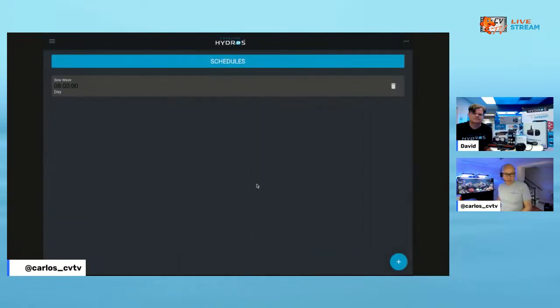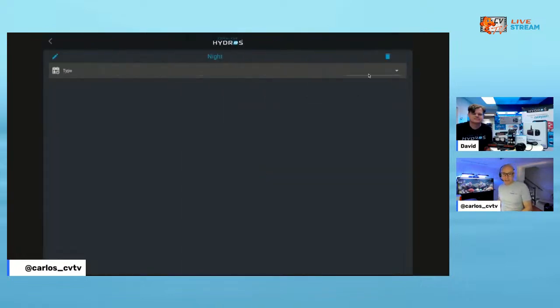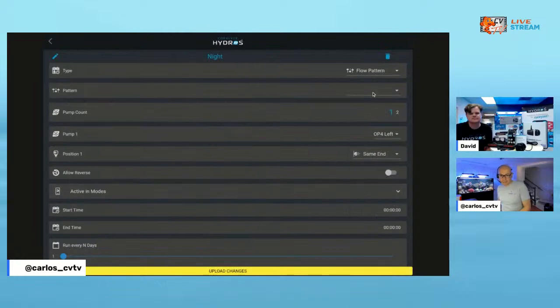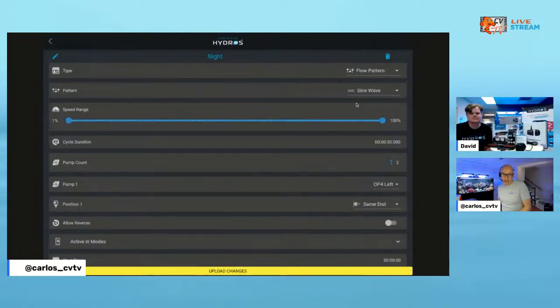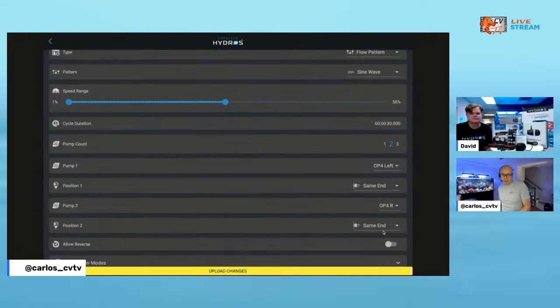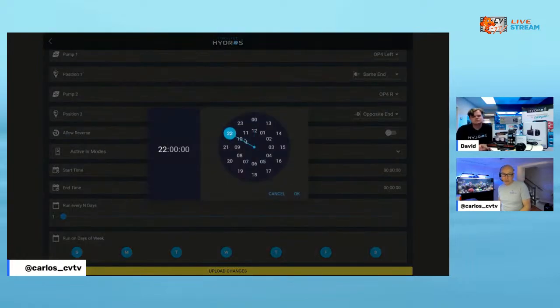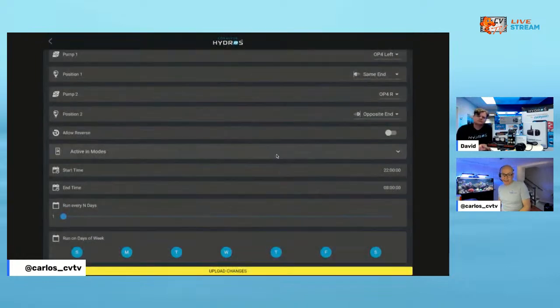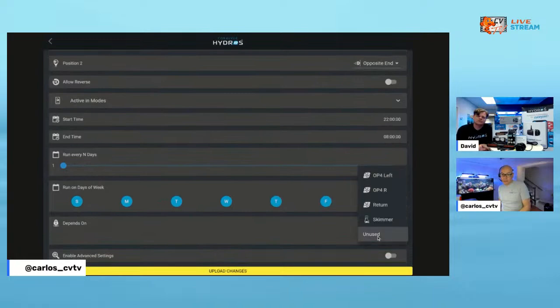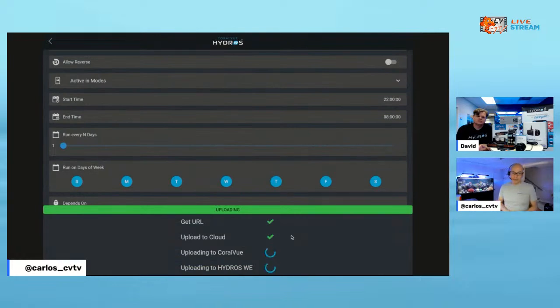Let's go ahead and add another schedule. Go to schedules here. And I'm going to call it night. Okay? And I'm going to go create. Then it's going to be a flow pattern. It's going to be a sine wave. You know what? I don't want it to run at 100%. Let's run it at 50%. Also, going to see two pumps, left and right. I'm going to make this one opposite end. Then I want this one to start at 2200 hours. And I want it to end at 8 o'clock in the morning the next day. And again, I want it to stop if the return pump is off. There you go. So let's go ahead and click that.